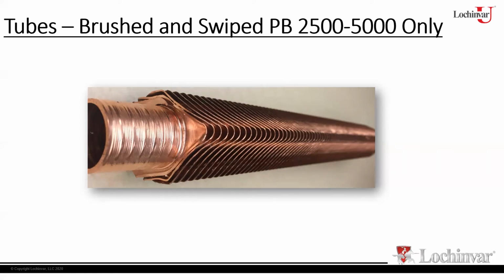So we're trying to fit these tubes better together. Also, doing that slows the flue gases down, gives you a little bit more restriction in the tube, which allows a little more contact time on the tube and gives you a little better heat transfer. All right. So again, as I mentioned, with 62 tubes, it takes a while to actually build this heat exchanger. So it's kind of a time-consuming process.